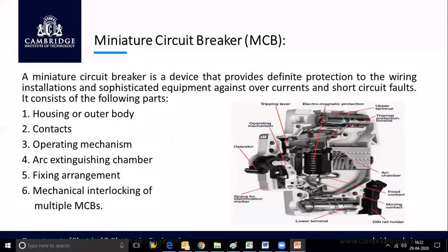Next, coming to the MCB, the miniature circuit breaker. Previously we discussed the fuse. A fuse is a basic protective device which is available at a cheaper cost. But whenever a fault occurs, the fuse immediately melts. Once the fault is cleared, we need to replace it with a new fuse material, otherwise we cannot get continuity of supply. So every time there is a fault, we need to replace the fuse, which takes more time. Therefore, there are certain disadvantages with the fuse.